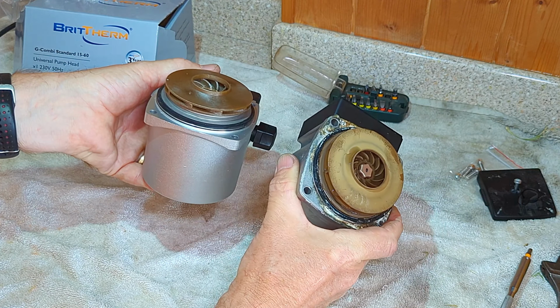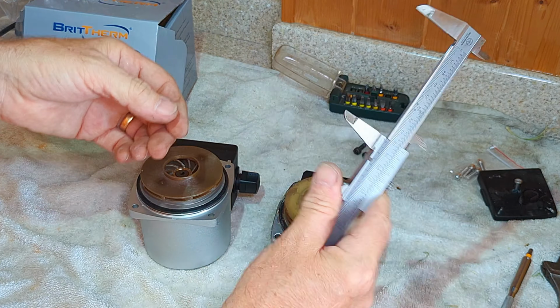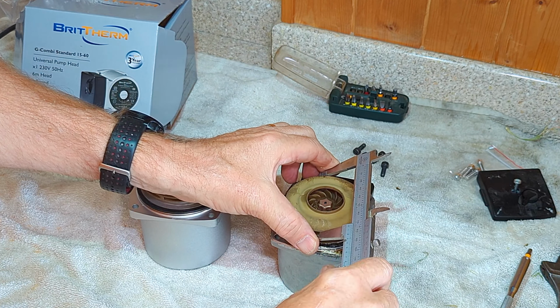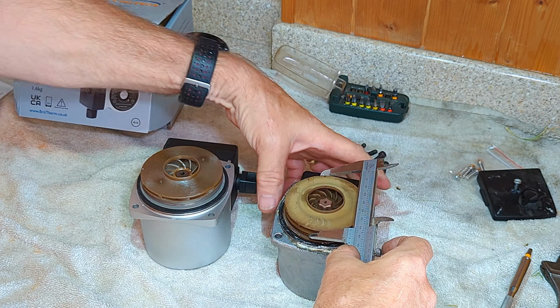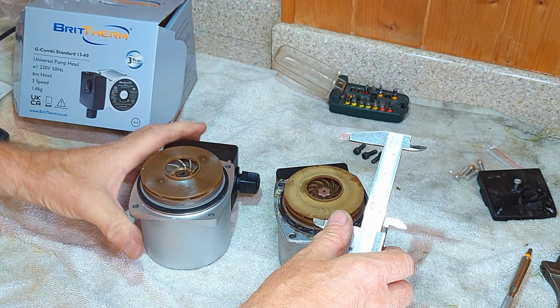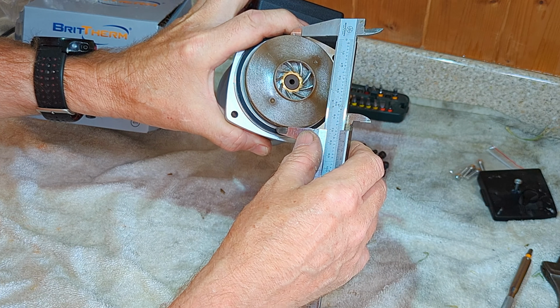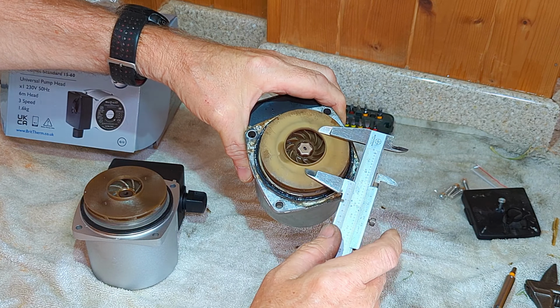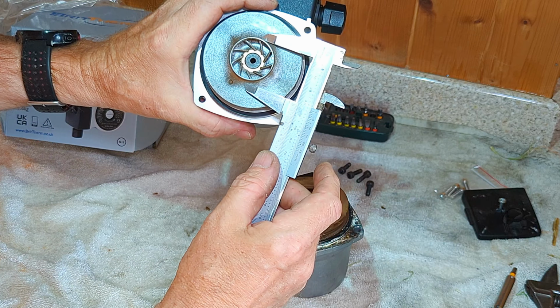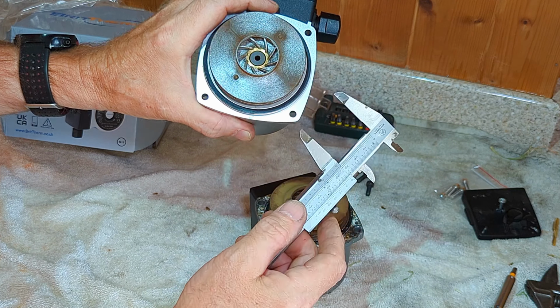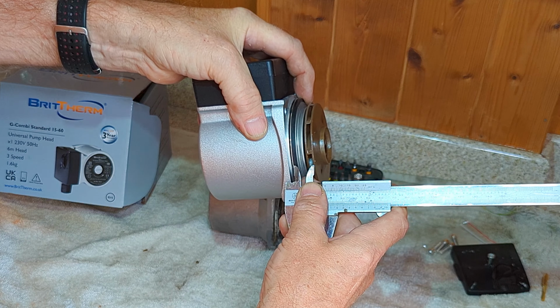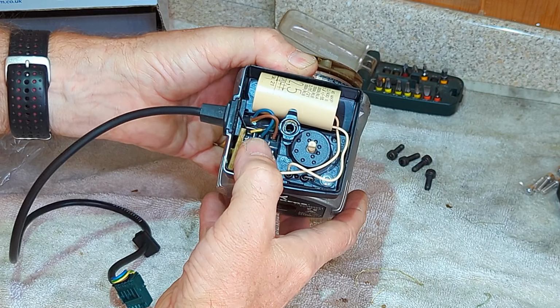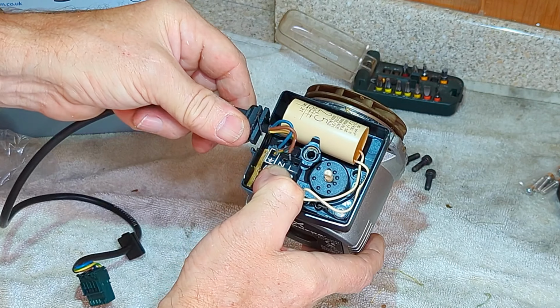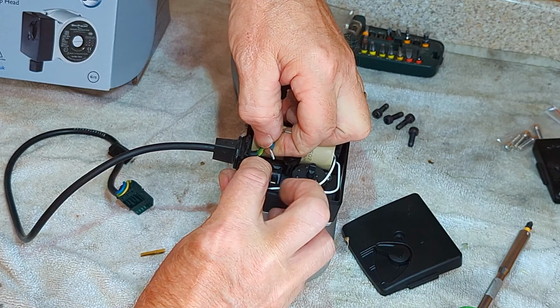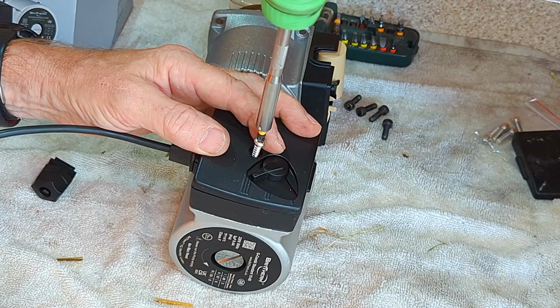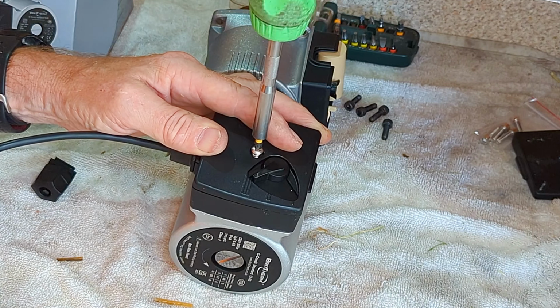Just a note, if you've got one of the newer Vaillant boilers which has 2 wires that come out of the pump, then you wouldn't be able to use this style of pump. Now I did do some measuring and checking just to make sure that the pump was going to fit into the old pump housing. The only real difference is the central impeller is just a little bit smaller than the original Grundfos pump. So I just removed the old wiring harness from the old pump and then fitted it onto the new BritTherm pump. And then just refit the cover and it's ready to go.